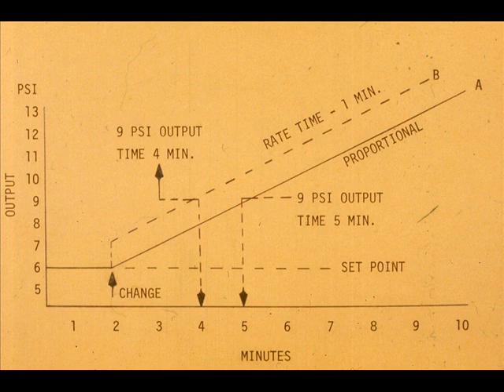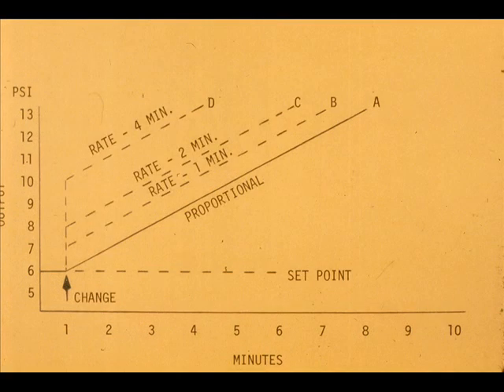At time five minutes, the proportional output is nine PSI. A rate time of one minute gives the same nine PSI at time four minutes. Curves B, C, and D show the controller output with different rate times. Each is compared to the proportional output curve A. It is obvious that a low rate time denotes less rate action.